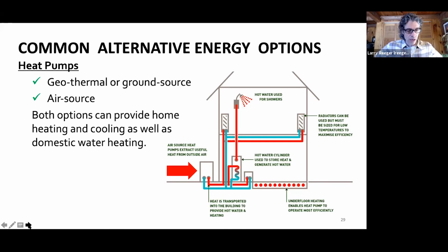Usually it's about a 40 to 50 degree rise, so we can take 55 degree temperature and turn it into about 95 degree heat and blow it. You can either circulate hot water or blow air into your home. That's how this home is heated with geothermal.